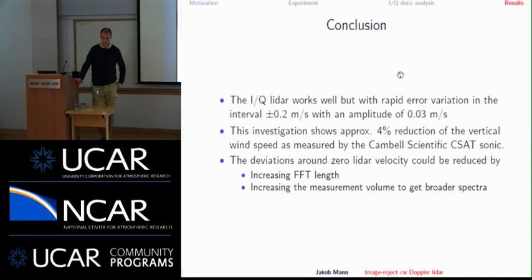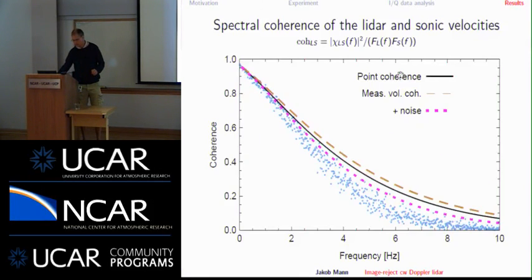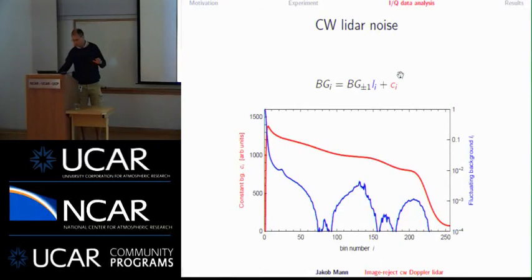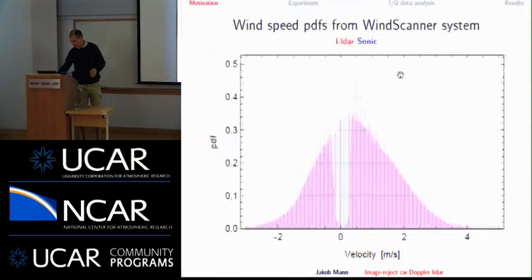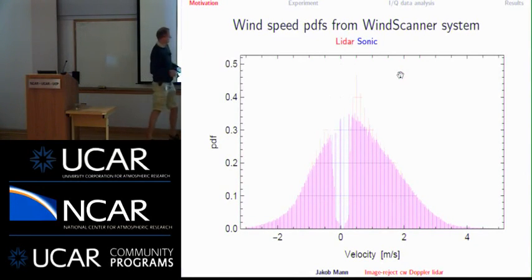What was your bin size? What FFT size were you using? 512 points, and it's a 100 megahertz sampling rate, so that corresponds to 15 centimeter per second steps in Doppler velocity. And usually we can get a much higher precision because we have power spectra covering many bins. But sometimes, and I think we can see it here, if we don't have a lot of power or the turbulence is low, then we can only get multiples of 15 centimeters per second. That's actually something you see here in the lidar histogram, that sometimes you get these lines, that is multiples of 15 centimeters per second.